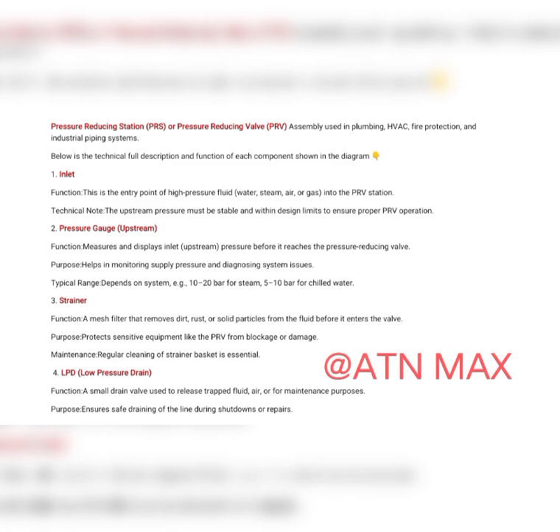3. Strainer. Function: a mesh filter that removes dirt, rust, or solid particles from the fluid before it enters the valve. Purpose: protects sensitive equipment like the PRV from blockage or damage. Maintenance: regular cleaning of strainer basket is essential. 4. LPD, low pressure drain. Function: a small drain valve used to release trapped fluid, air, or for maintenance purposes. Purpose: ensures safe draining of the line during shutdowns or repairs.